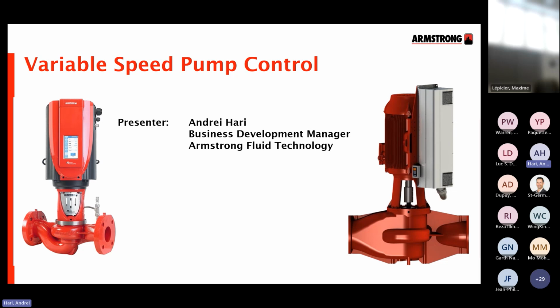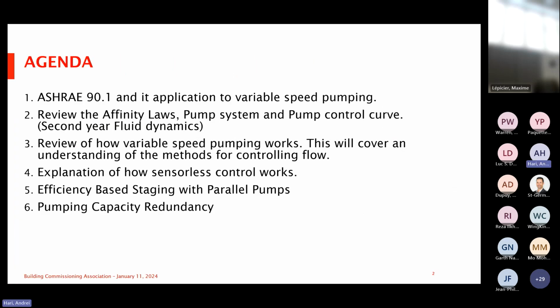So without further ado, first of all, variable speed pump control. The agenda today: first, we're going to go through ASHRAE 90.1 and its application to variable speed pumping, a review of the affinity laws, and then the pump system and pump control curve, which is basically covering second-year fluid dynamics for those of us who are mechanical engineers. Then a review of how variable speed pumping works in a system, and an understanding of the methods of controlling flow. Then an explanation of how sensorless control works. After that, efficiency-based staging, what it is as it applies to parallel pumps, and then a little discussion on pumping capacity redundancy and the difference between redundancy and N+1 design. And at any time, if anybody has a question, please feel free to ask.